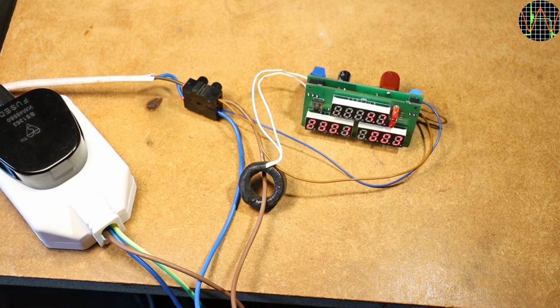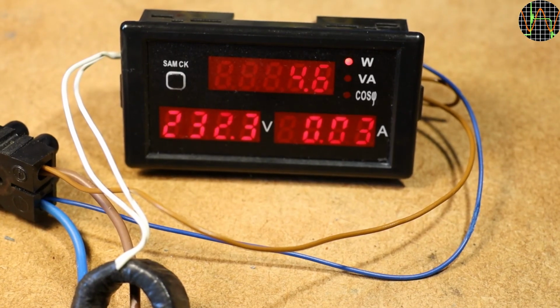I can't show the other readout modes because it would be far too dangerous to touch the module and press the button without a cover. So I decided to put that back on, which makes the display a lot more readable too. It's the same test as before, and the active power is shown as 4.6 watts. That's the power actually used by the light and which you pay for. I have no idea, by the way, why this button is labeled SAMCK.